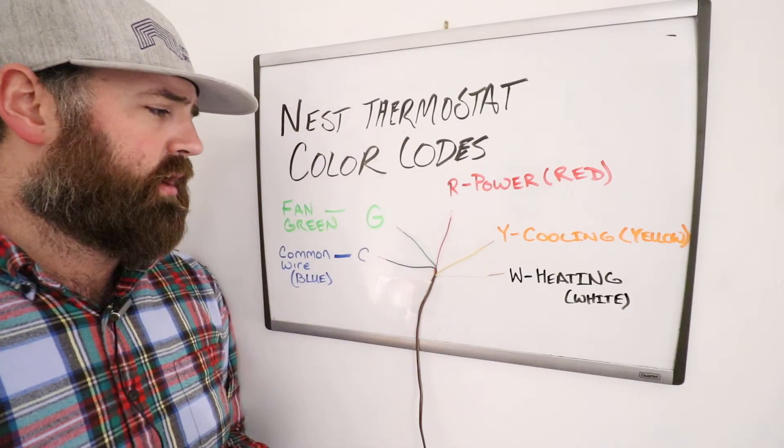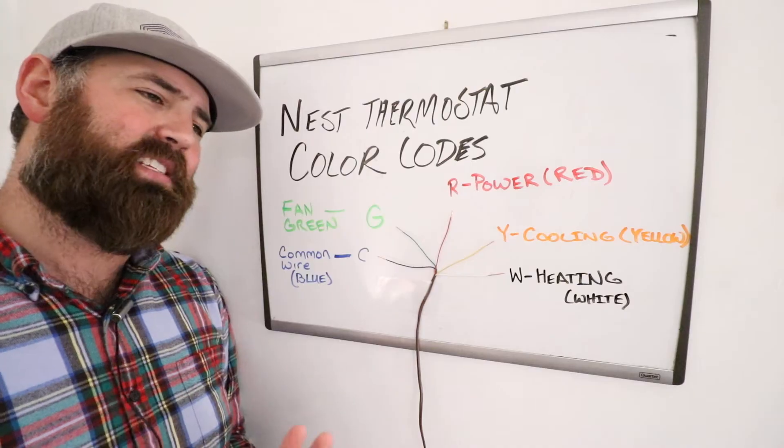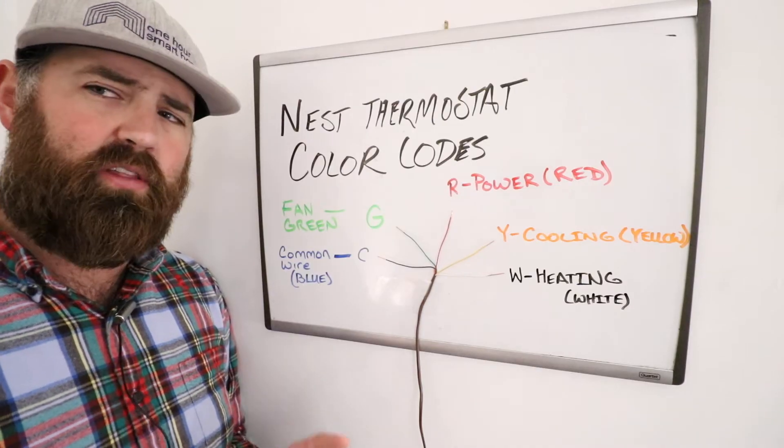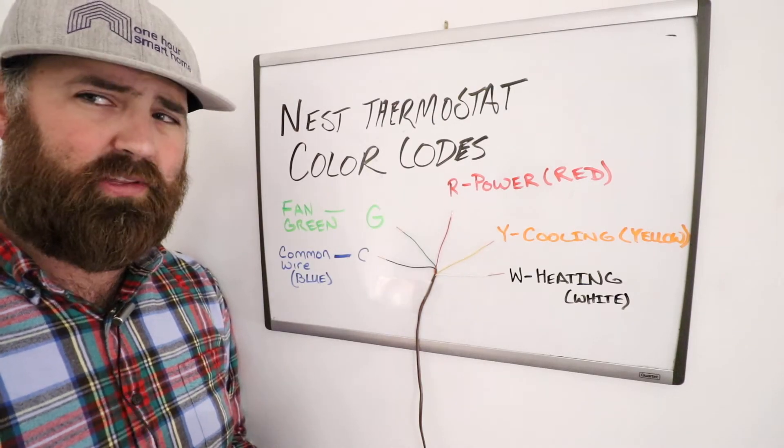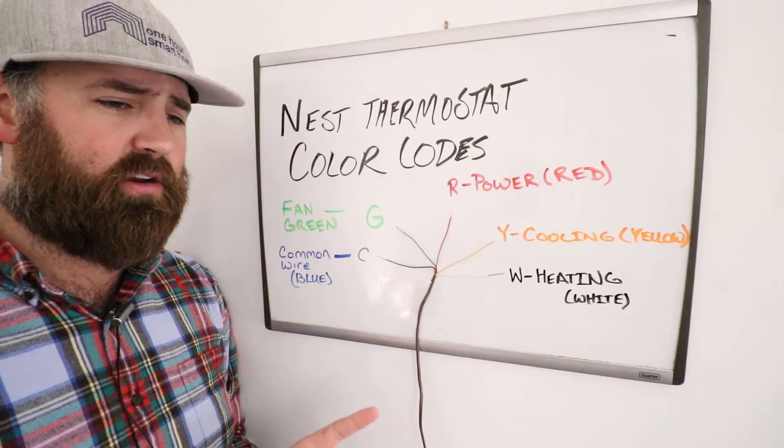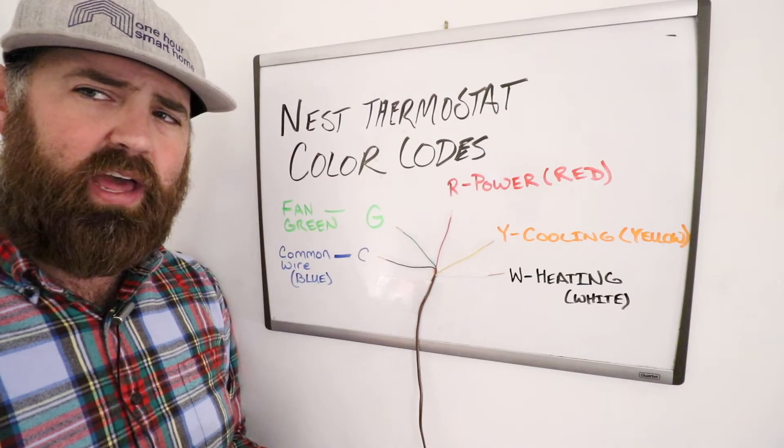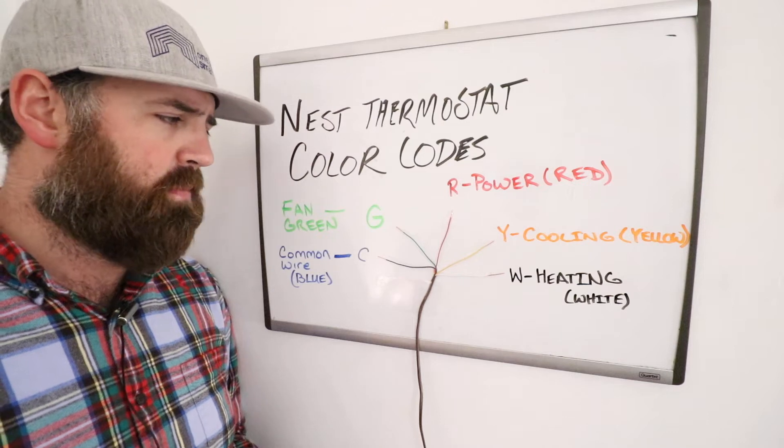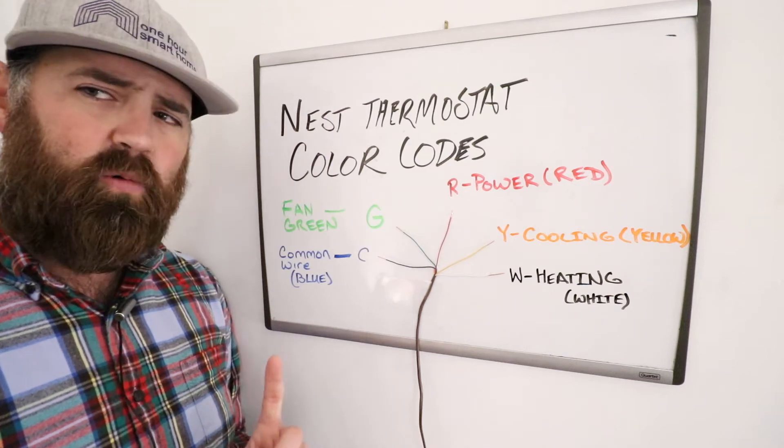The G-Wire is actually not necessary, but adds other features. And we do have another video that shows you what you can do with the G-Wire if you don't have a C-Wire and you need one, but we're not going to cover it in that. You can look at one of our other videos if you want to learn more about it. But the fan wire, what it does is it allows you to control your fan inside your HVAC system without turning on your air conditioning or your heating.